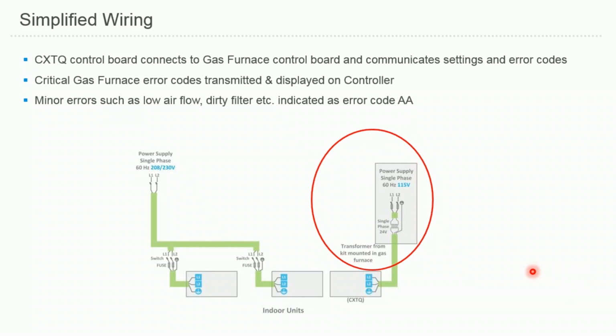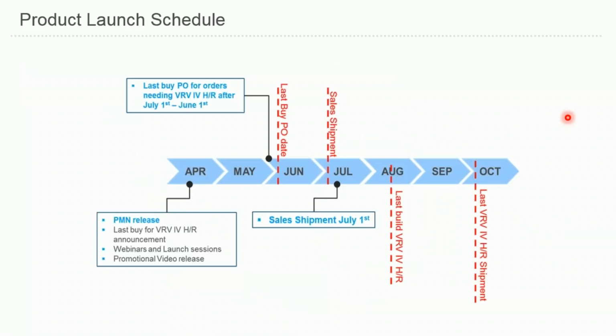For major issues, major error codes such as communication problem or power supply problem, there will be a dedicated error code for those. Or if you're seeing minor errors like dirty filter, low air flow rates and things like that, you will be seeing a common error code, which will be AA showing up on your navigation controller.